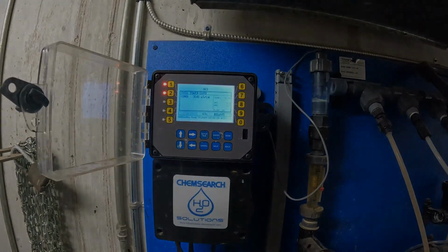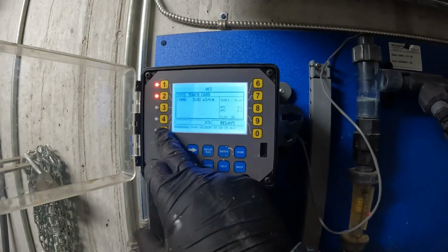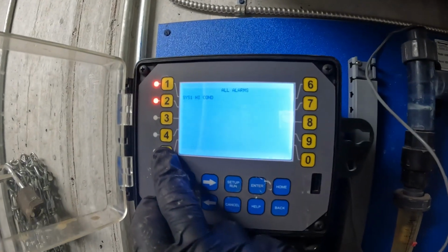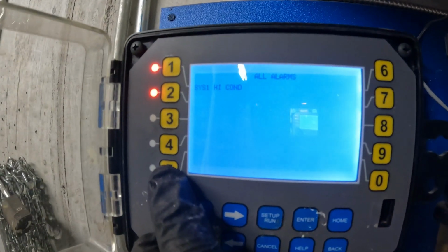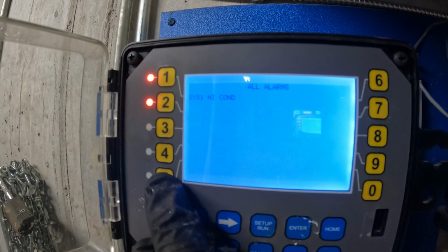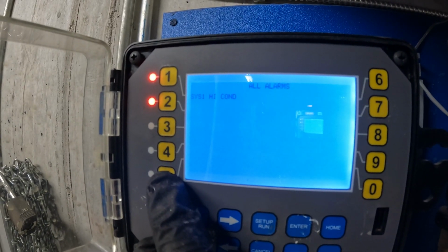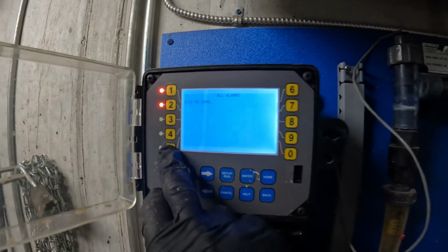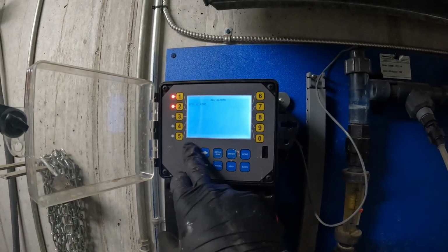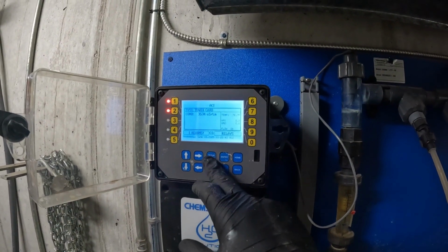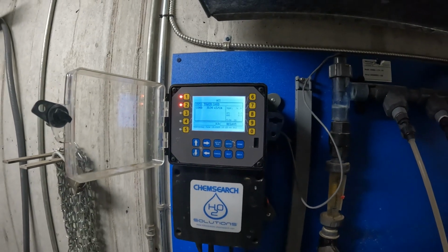Now you may have noticed that there was an alarm on this tower. If you select the alarm icon, you will see what the issue is. This particular alarm was for high conductivity. This was due to the tower not running when the rep arrived since it was a cool morning. When there is no flow in the manifold, the controller will not initiate the relays. The tower turned on shortly after the rep arrived and the alarm will correct itself shortly.